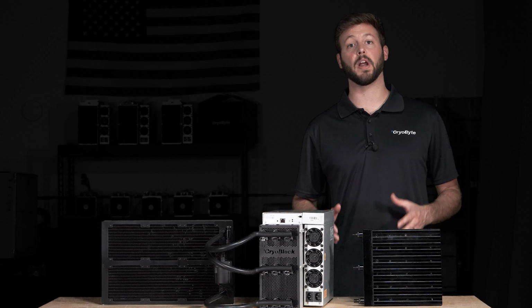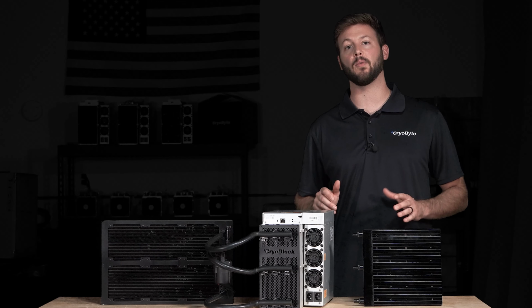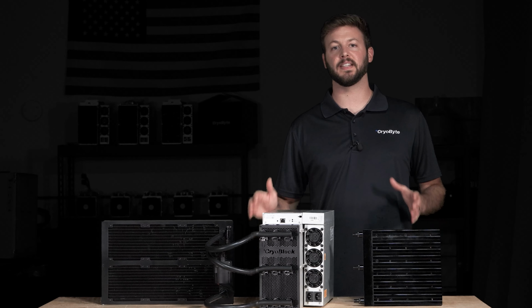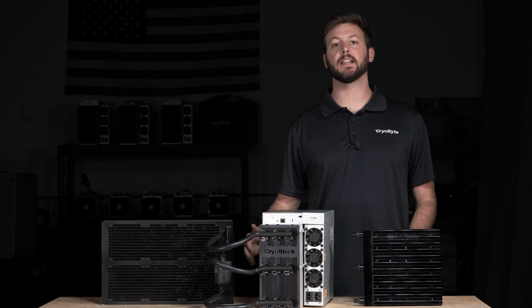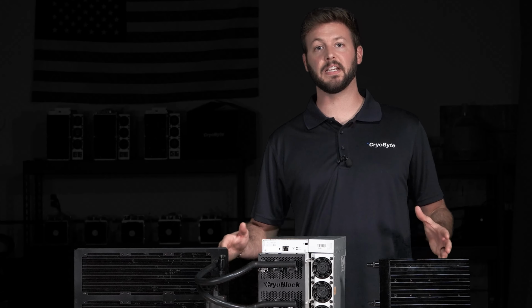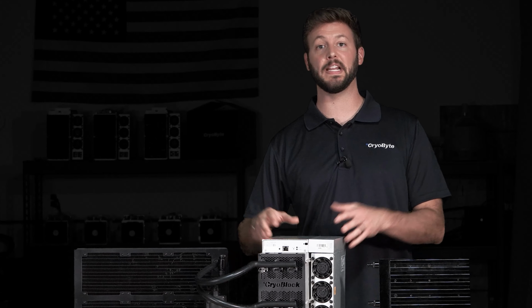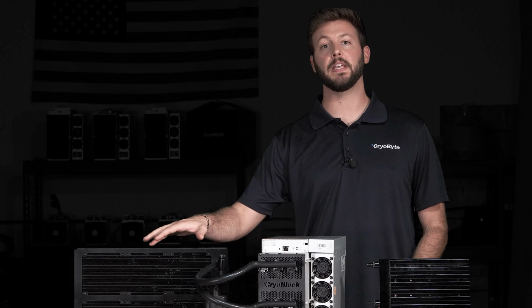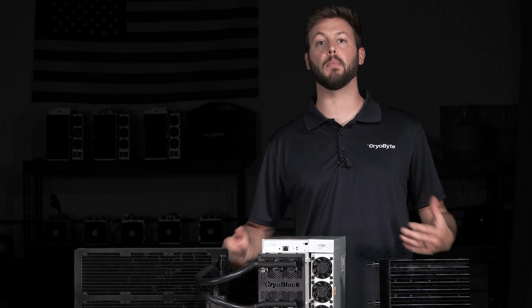So much so that we're able to utilize a process called hot water cooling. Hot water cooling is exactly what it sounds like: it utilizes an elevated coolant temperature, and because of the temperature difference between our coolant and ambient air, our final heat rejection unit is able to operate much more efficiently.